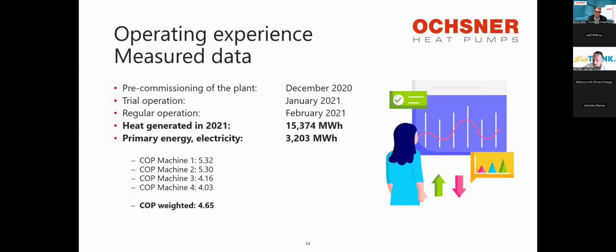This is the plant, so it's a very small room which was built in the cellar, and these 4 heat pumps were installed. So really a narrow installation of all these heat pumps. And here you can again see the weighted COP, because with the 2 heat pumps with the higher source temperature, you have a COP of above 5. And with the other 2 still above 4, so you have a weighted COP, so efficiency, of 465%. So out of 1 megawatt hour of electricity, you get 4.65 megawatt hours of heat. And this is a very, very short return on investment time, as you have seen before.